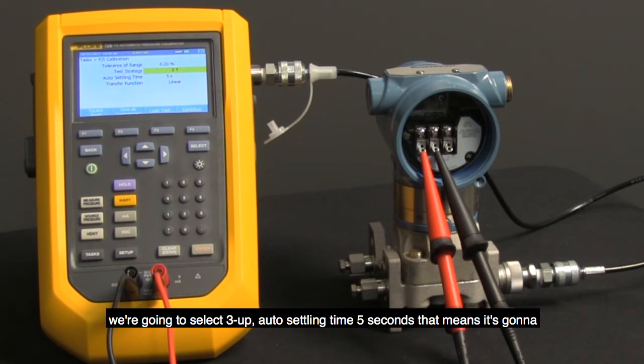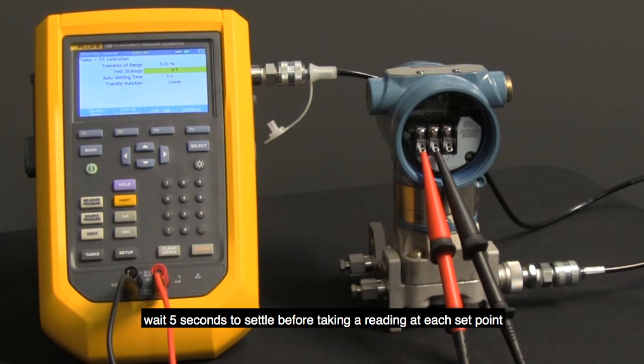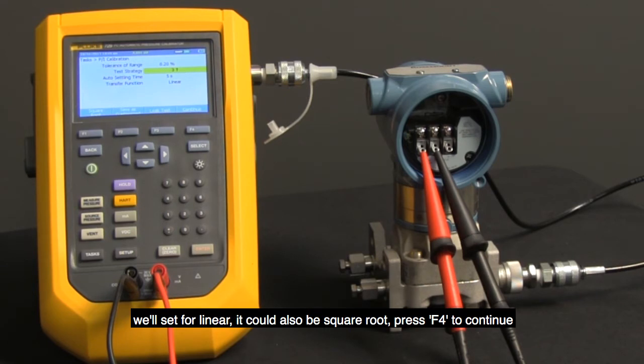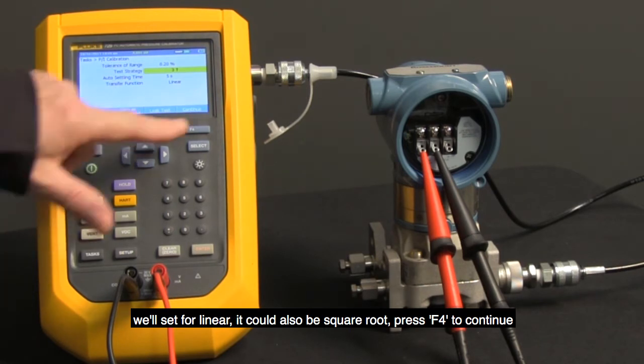Auto settling time, five seconds. That means it's going to wait five seconds to settle before taking a reading at each set point. And then the auto transfer function we'll set for linear. It could also be square root. Press F4 to continue.